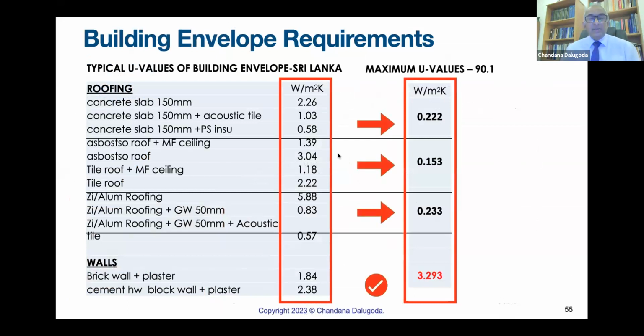I will just give a glance. This column gives you the Sri Lankan U values that we use in normal circumstances. And if you want a green building, this is what we should be using. Or if it is a net zero building, we should use these values. For instance, a concrete slab, 150 millimeter. Our U value is 2.26, but it has to be dropped to 0.22 in a net zero building. How do we do that? Thermal insulation, air gap, whatever. Similarly, asbestos roofs, zinc alum roofs. Walls, we are good: 1.84, requirement 3.2 already.